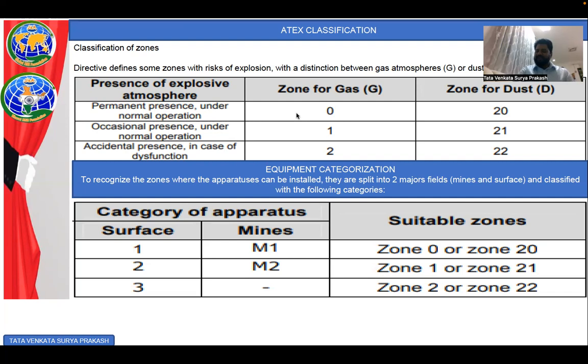Zone 0 is where the explosive environment is permanently present, and for dust it is called zone 20. For occasional presence under normal operation, it is called zone 1, and for dust it is called zone 21. For accidental presence, where it is present only now and then or rarely, it is called zone 2, and for dust it is considered zone 22. So equipment categorization is based on the zones. For example, to recognize the zones where the apparatus or equipment can be installed, they are split into two major fields, mines and surface, and classified with the following categories. For example, the category of apparatus in surface is called 1, and when it goes to mines, it is called M1.